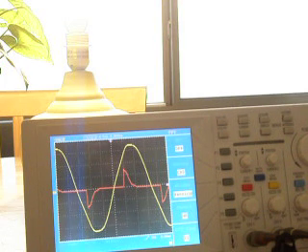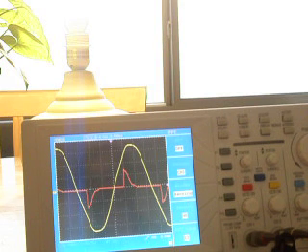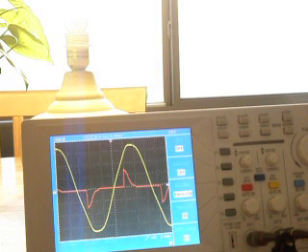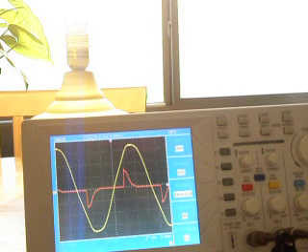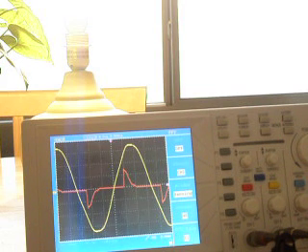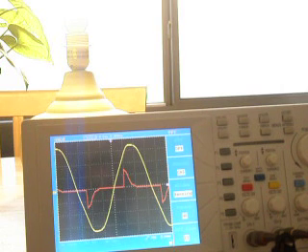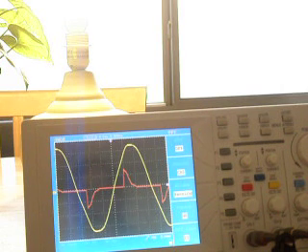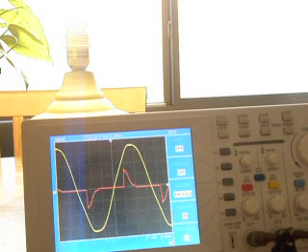And that's quite a concern because that's the inverter system pulling off power from the power system. So what it's doing is it's pulling its current impulses from the main system, and the problem with that is it creates harmonics. Any time you do a non-sinusoidal draw off the power system, you get this harmonic frequency effect.